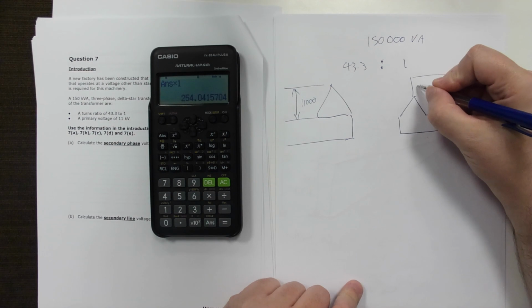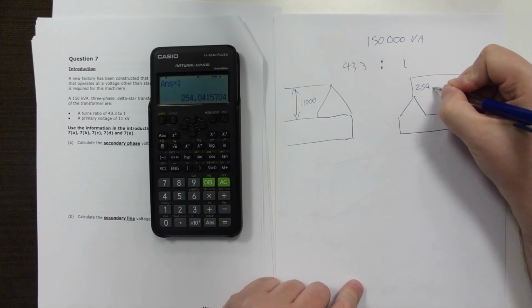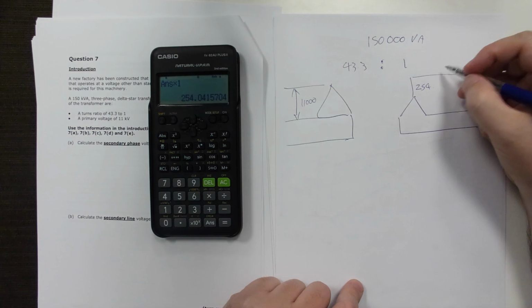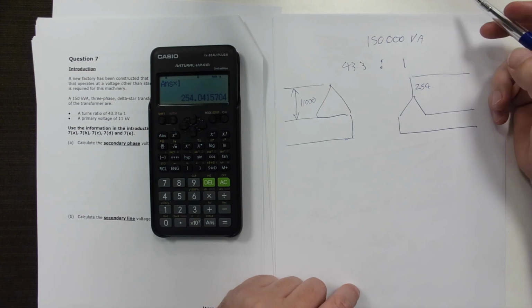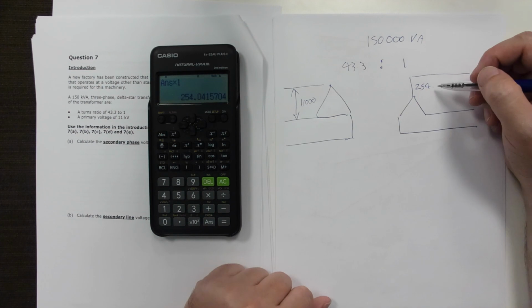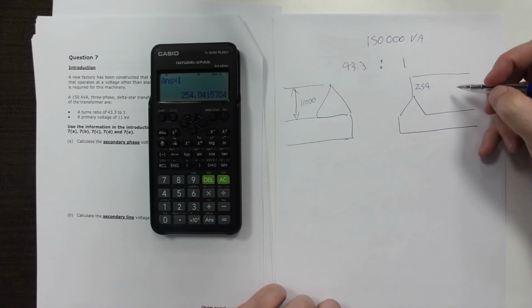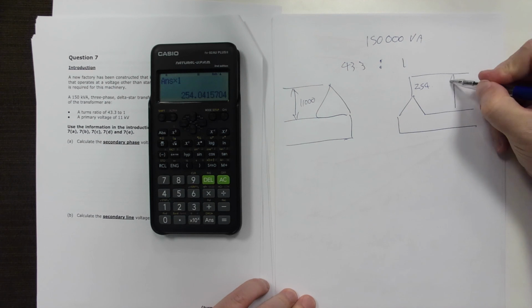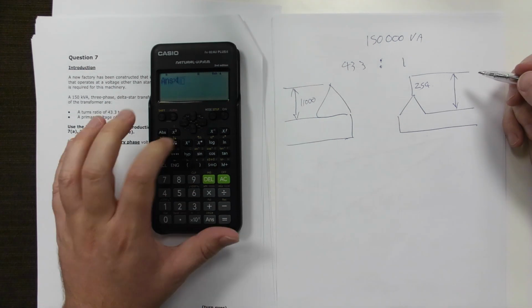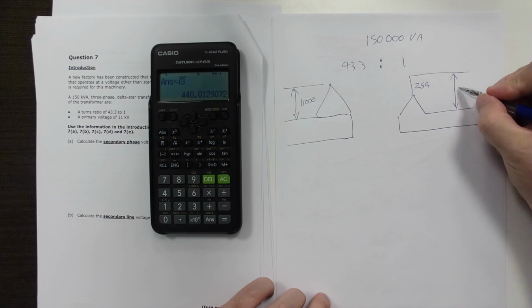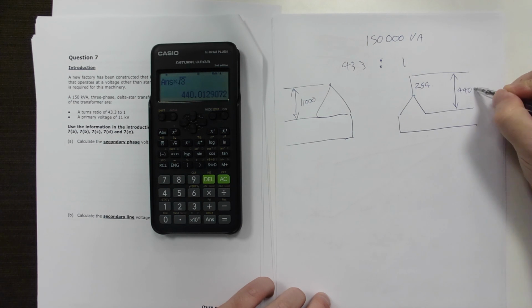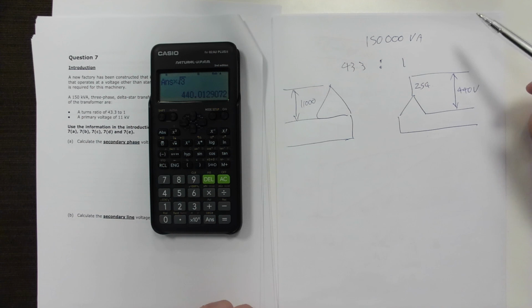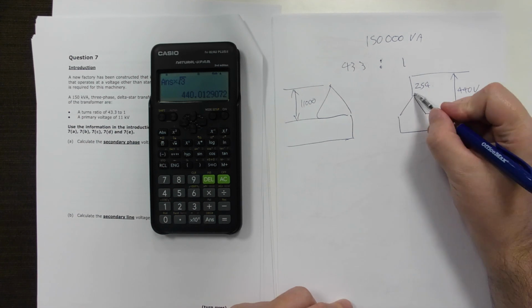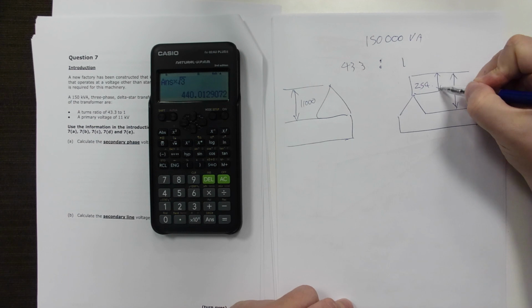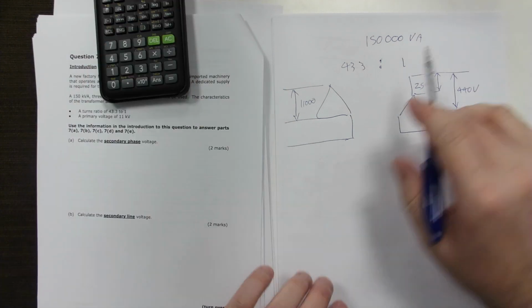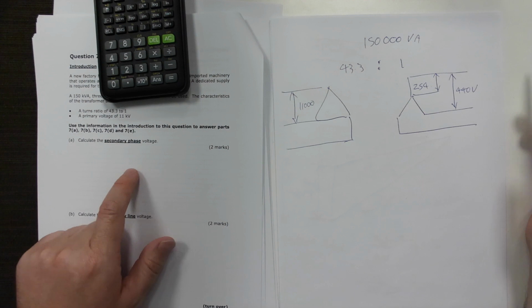We get our voltage here of 254.04. So just leave it as 254 for this one. Then we're just going to go to 0 decimal places. And then to work out our voltage here, times by square root of 3, and we get 440 volts. Now, that is generally the type of thing they will ask you to do in almost every exam, so I always start by that. It's just write down your voltages. It's probably going to ask us for current shortly.